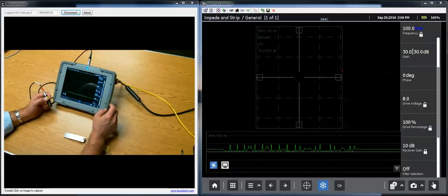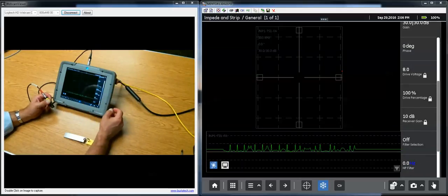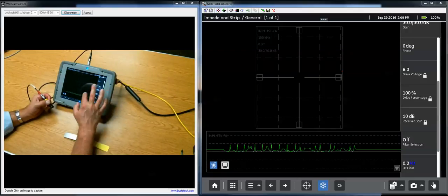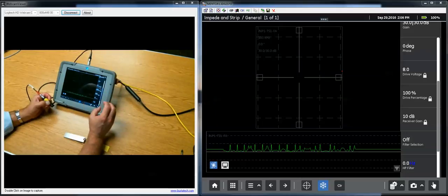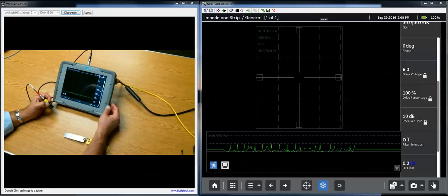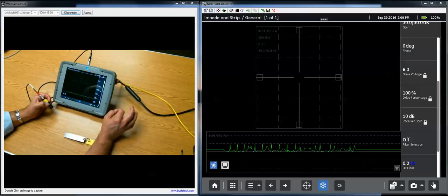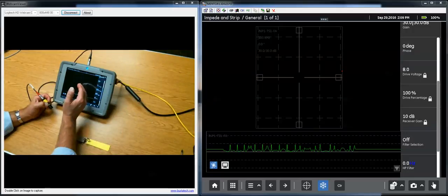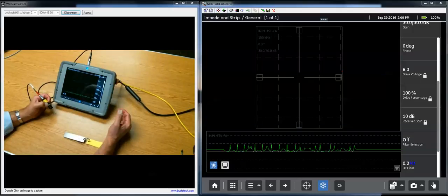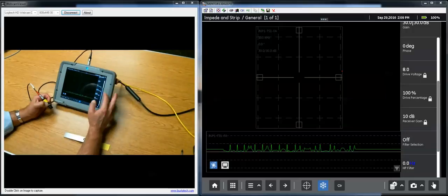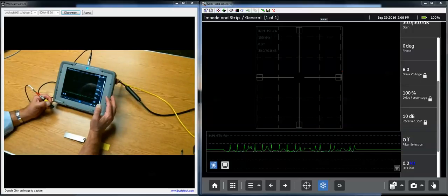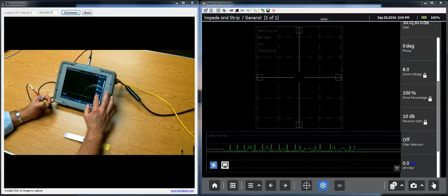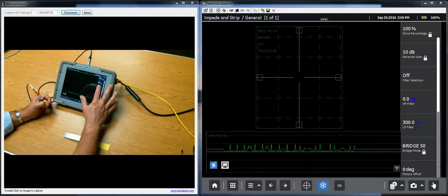Receiver gain. One thing that causes a lot of confusion in newcomers to the Mentor instrument over some other Eddy Current instruments is they expect the amplitude of the signal to change when they change receiver gain. That will not happen in the Mentor. This control is only used to avoid saturating the amplifiers on the input of the instrument. If you are getting a sharp knee in your liftoff signal or some other indication that you're saturating amplifiers or saturating the coils, try reducing your receiver gain. In general you will not see a change in amplitude of the signal as a result of that, and that's good. That's the instrument behaving as intended.